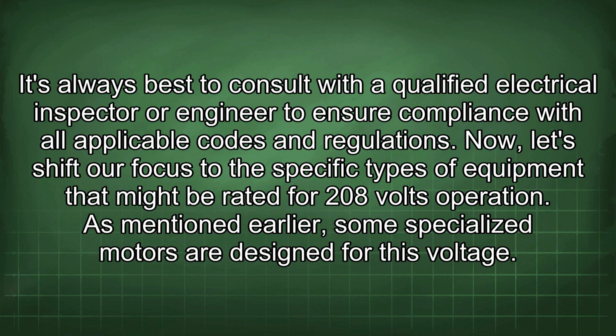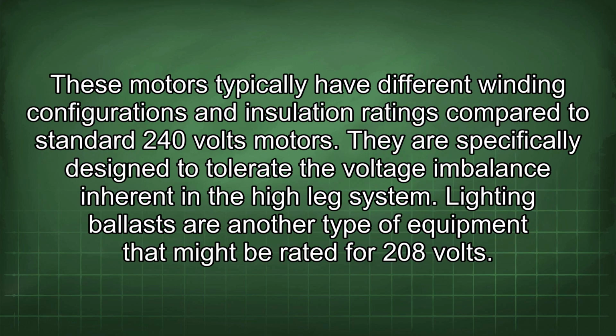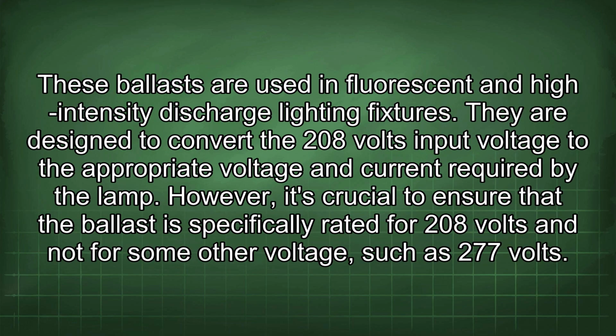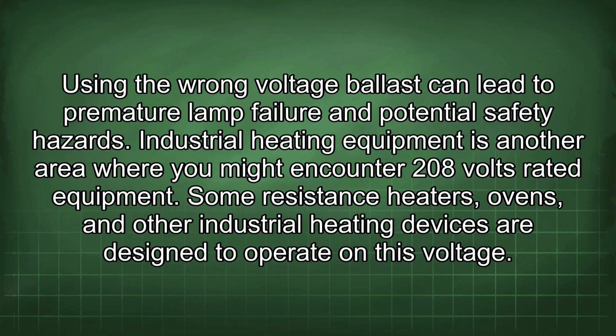As mentioned earlier, some specialized motors are designed for this voltage. These motors typically have different winding configurations and insulation ratings compared to standard 240 volt motors. They are specifically designed to tolerate the voltage imbalance inherent in the high leg system. Lighting ballasts are another type of equipment that might be rated for 208 volts. These ballasts are used in fluorescent and high-intensity discharge lighting fixtures. They are designed to convert the 208 volt input voltage to the appropriate voltage and current required by the lamp. However, it's crucial to ensure that the ballast is specifically rated for 208 volts and not for some other voltage, such as 277 volts. Using the wrong voltage ballast can lead to premature lamp failure and potential safety hazards.